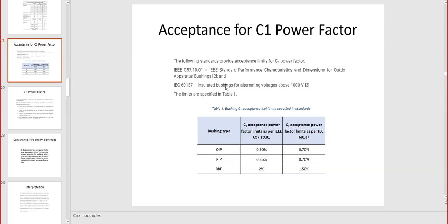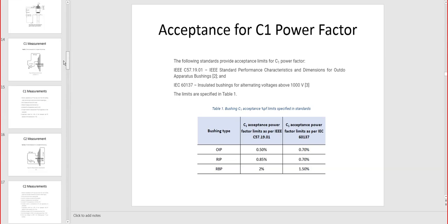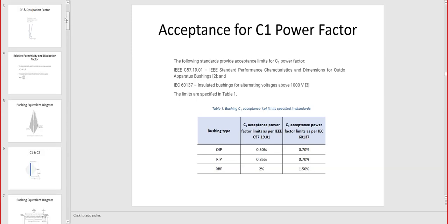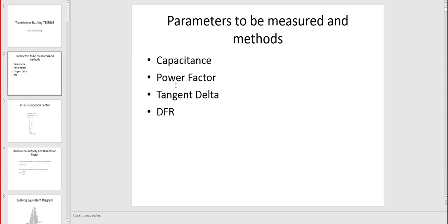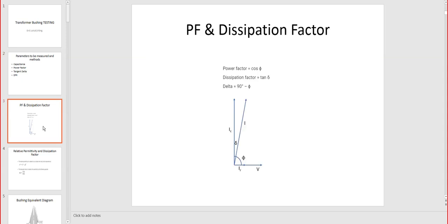Good question. So any other question? Any question is a good question. So once again, going back, what we went through is the test that we need to do to test correctly the bushing. As a minimum, it is the capacitance C1, C2, from the top to the tap and from the tap to the ground. Then the power factor and dissipation factor, so power factor, tangent delta, dissipation factor, all at 60 Hertz. All these readings are at 60 Hertz, but then we have dielectric frequency response that is for a range of frequencies. And we should have graphics that can be compared to the readings. So don't forget this slide, that is crucial to understand what we are reading and what kind of values we want.